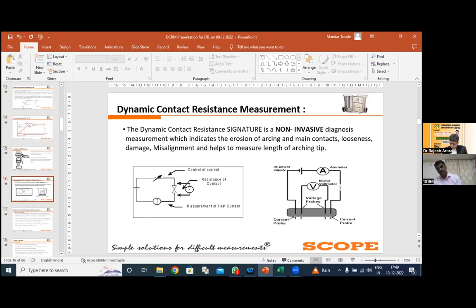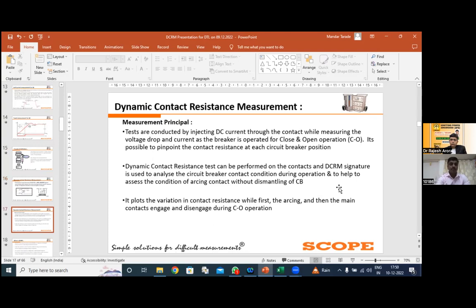Moving ahead, the dynamic contact resistance test is a very, very important test, which is basically a non-invasive test. Why is it non-invasive? Because we perform the test without opening the breaker. With the help of this test we can identify if there is any pitting, any contact erosion, or any carbon deposition at the contact level. So this test plays a very significant and important role.